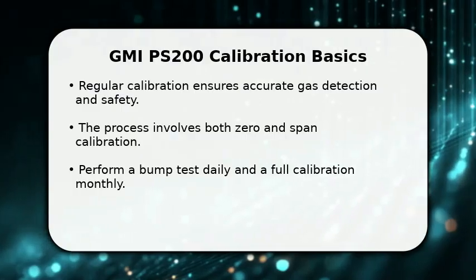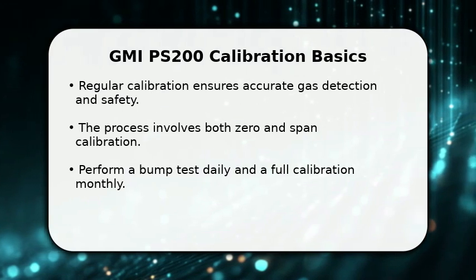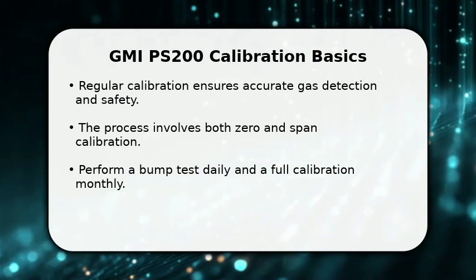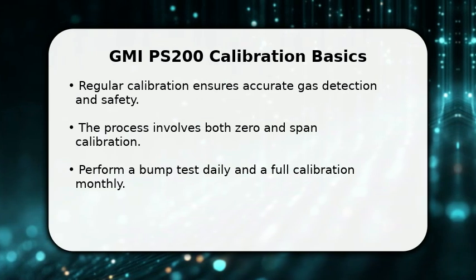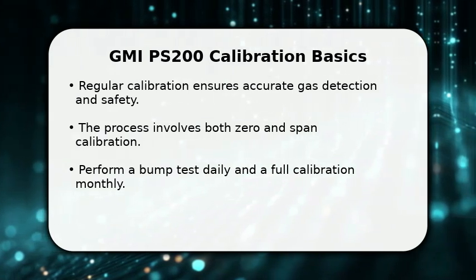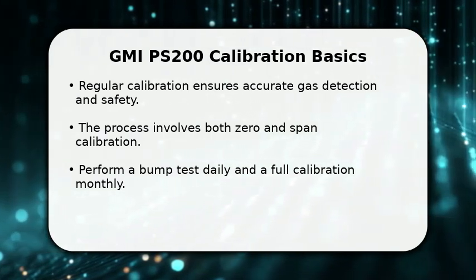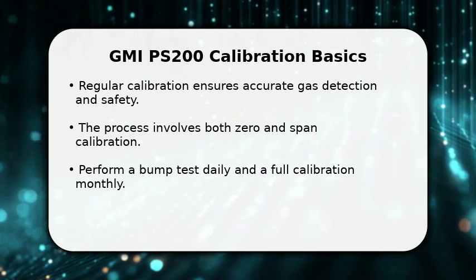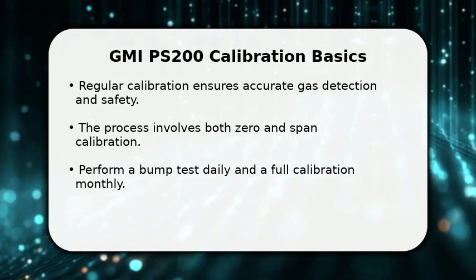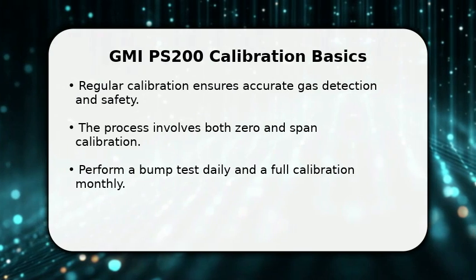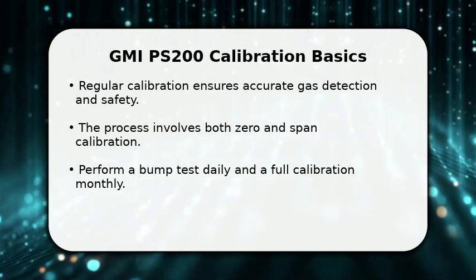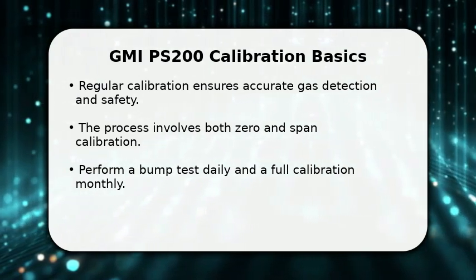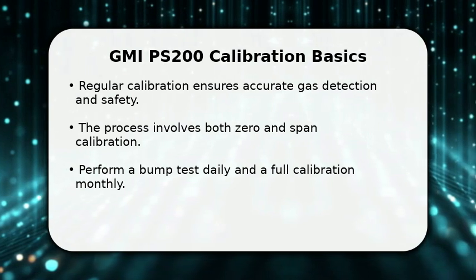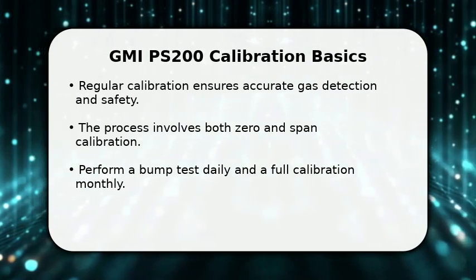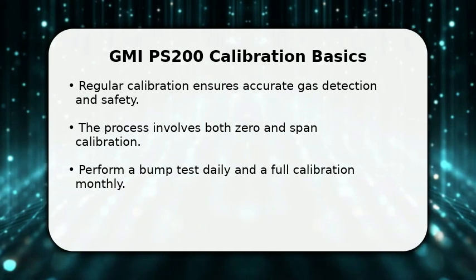In this video, I will explain how to calibrate your GMI PS200 gas detector. Maintaining your device through regular calibration is crucial for accurate gas detection and ensuring safety in hazardous environments. We will cover both zero and span calibration, which are essential steps. It is recommended to perform a quick bump test daily and a full calibration at least once every month to ensure optimal performance and compliance with safety standards.